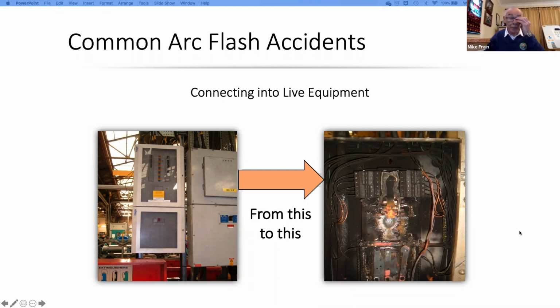This is a company in the UK, and they've got a guy connecting cables into this 200 amp circuit breaker panel on the left-hand side. It was at high level, so they had to access it using a mobile elevated work platform. And it became this on the right-hand side, for reasons we don't properly know, even to this day. But the fact is, the guy was pulling cables in there, and there's a possibility that there was a manufacturing defect inside the busbar stack within the MCB part of the distribution board. And we think that, because of the disturbance, it created a flashover within the unit itself.